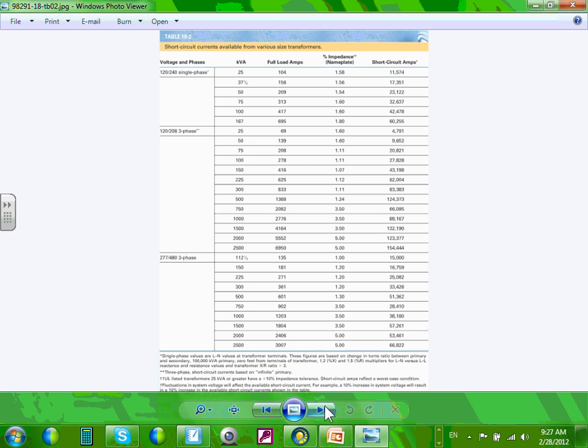Can you look at this one, please, on page 423? Page 423 gives you the available short circuit from a 500. This is only for one transformer, only for one voltage. That's the disadvantage. Imagine if you want to change the transformer or the voltage, you have to have another table. This one is for a 300 kVA transformer, three-phase, 2% impedance, and they're giving it to you for four voltages: 208, 240, 480, and 600.